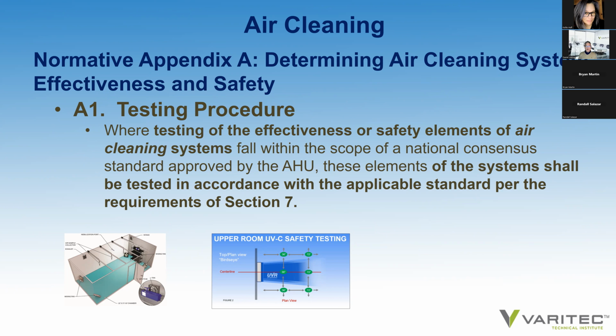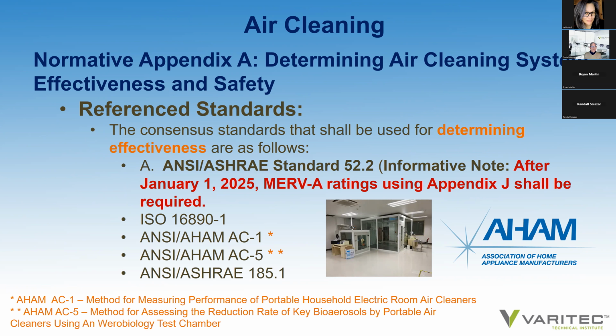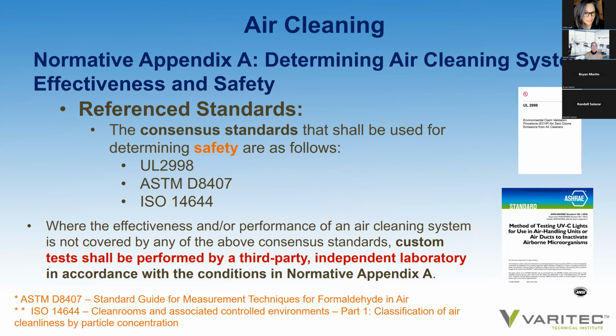Normative Appendix A is used for determining an air cleaning system's effectiveness and safety as well, where testing of the effectiveness or safety elements of air cleaning systems fall within the scope of a national consensus standard. So what are those standards that Normative Appendix A is requiring for measuring the effectiveness of removing infectious aerosols? Normative Appendix A is saying that ASHRAE Standard 52.2 must be used, and MERV A ratings will be applied by 2025. It leans on ISO 16890, which is an international filtration standard. It relies on ANSI AHAM AC1. And then for UV lighting, ASHRAE Standard 185.1. These are the testing requirements for these technologies.